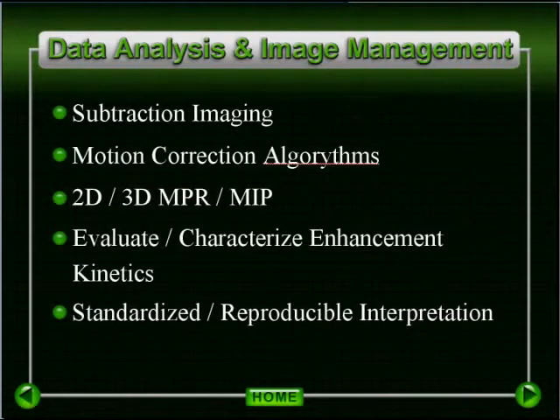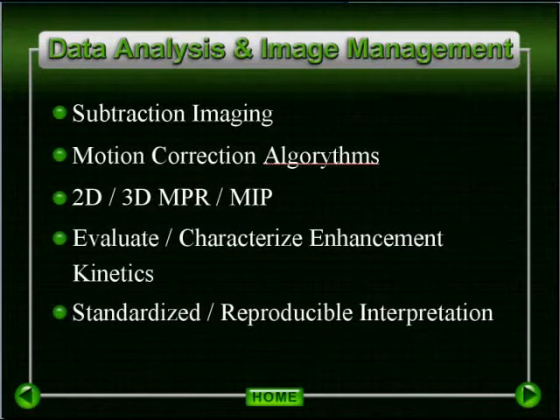You need a system with the ability to perform automated subtraction imaging, preferably with the use of motion correction algorithms. You also want the ability to perform 2D, 3D MPR, and MIP images. It is important to be able to evaluate and characterize enhancement kinetics automatically and with optimal accuracy. And finally, performing all of this in a standardized and reproducible method which facilitates image interpretation.